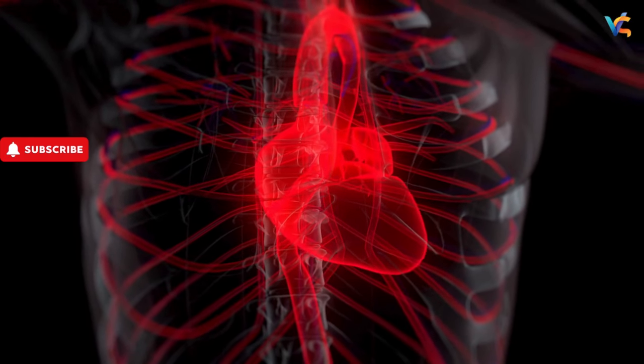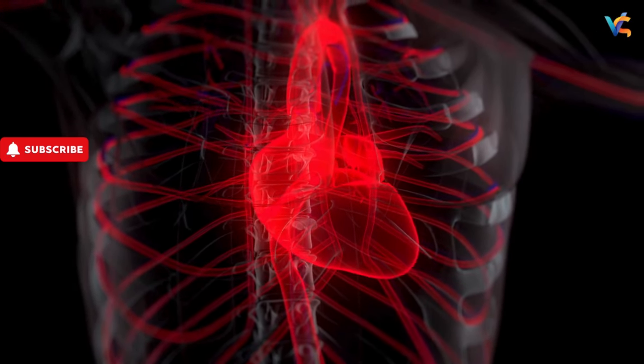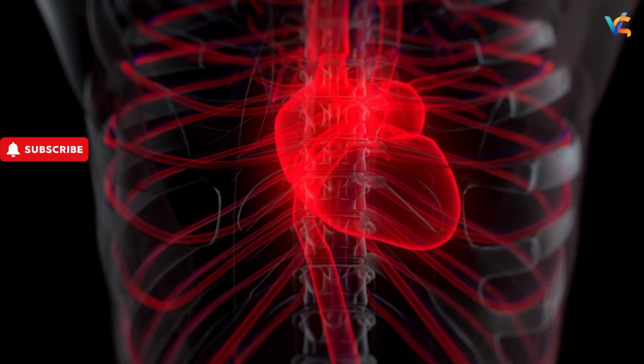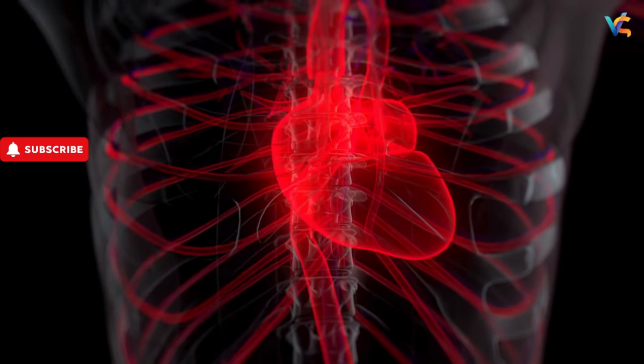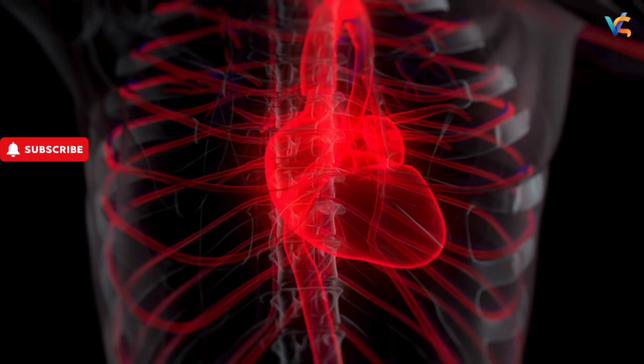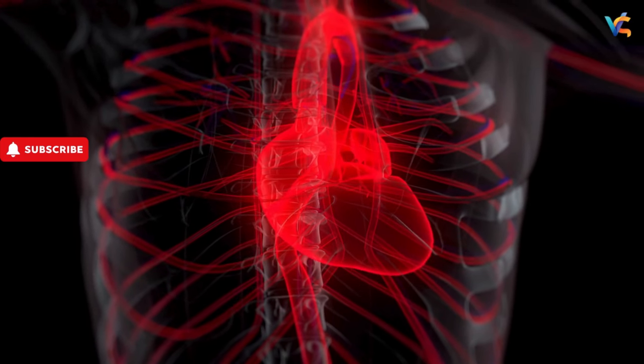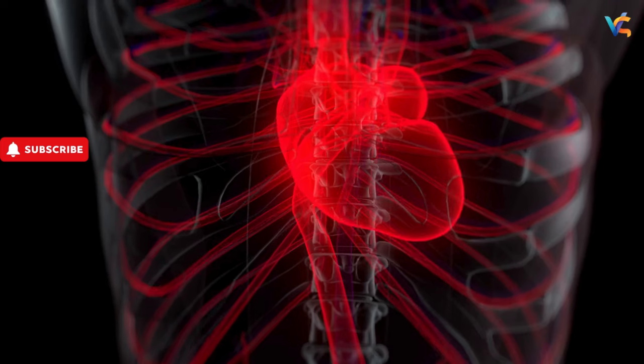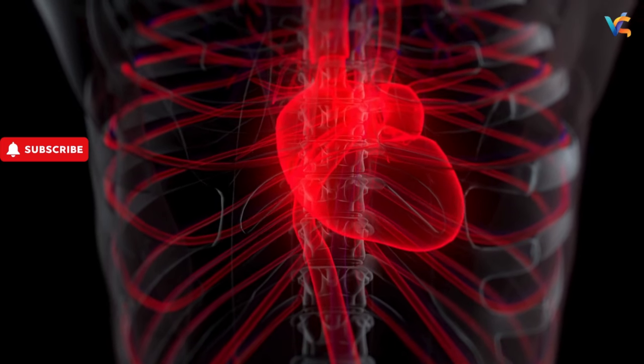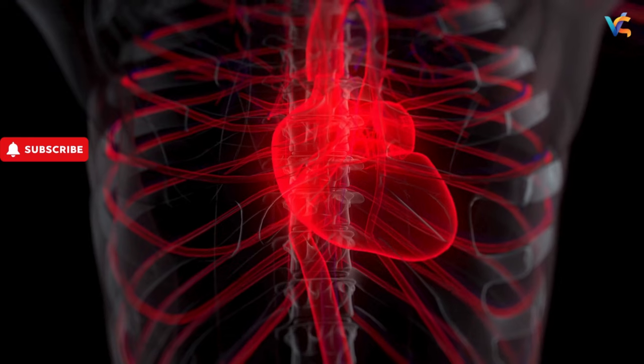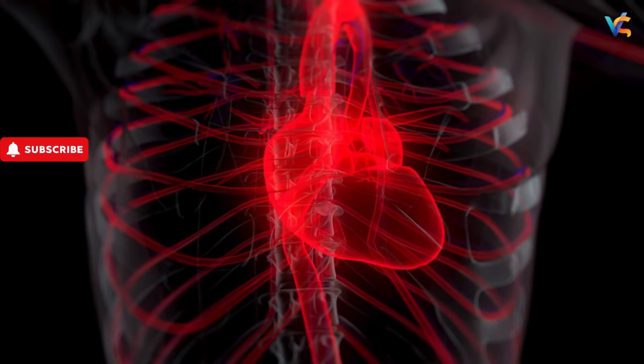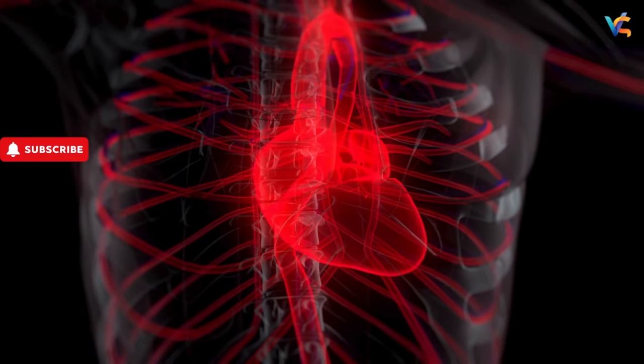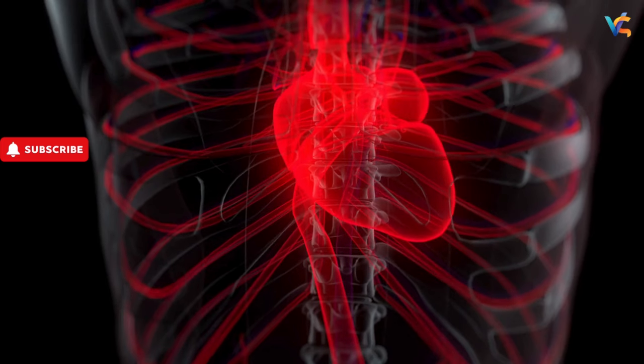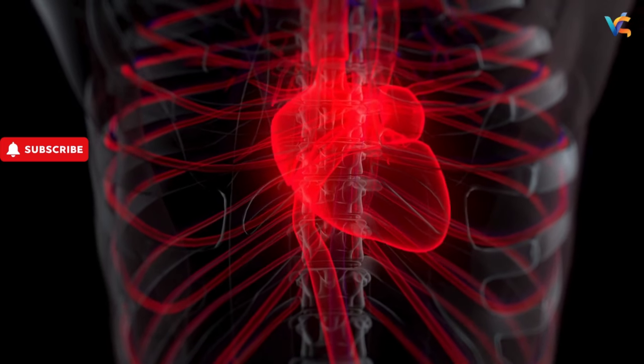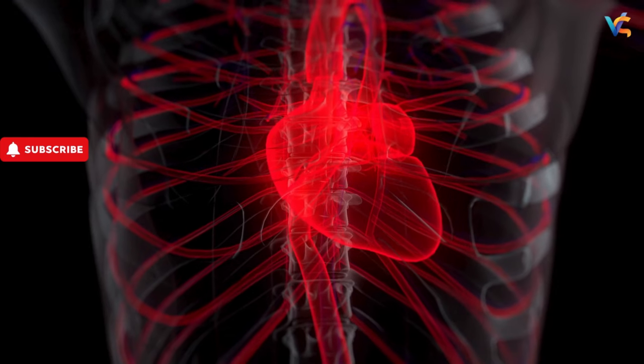But I can imagine something like that could get tricked, maybe. You're absolutely right. For example, a simple activity sensor might mistake shivering or even a tremor for physical activity and inappropriately speed up the heart rate when it's not needed. So how do they deal with that? Well, to tackle this, some of the newer devices actually combine two different types of sensors, maybe a motion sensor plus a breathing sensor, to get a more accurate picture and confirm that an increased rate is truly needed.